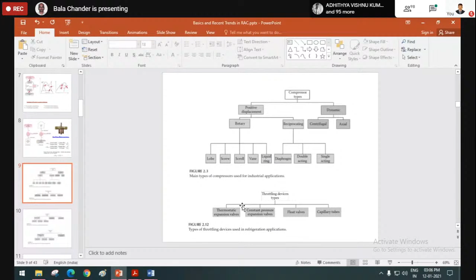So capillary tube, because of its simple construction and because the cost of the component is very low. Mostly it is preferred in small capacity applications where there is no need for load variation. If there is no much load variation in the evaporator side, I can go for the capillary tube. If there is load variation in the evaporator side, that is, in the amount of heat being taken in the evaporator, they prefer to go for the TXV, the thermostatic expansion valve. Another one is constant pressure. Generally the thermostatic expansion valve is preferred.